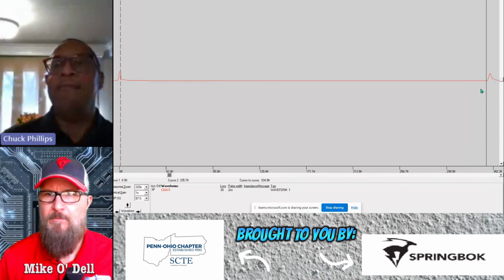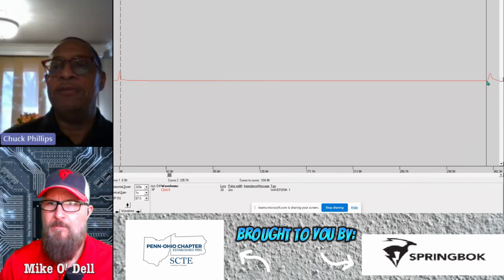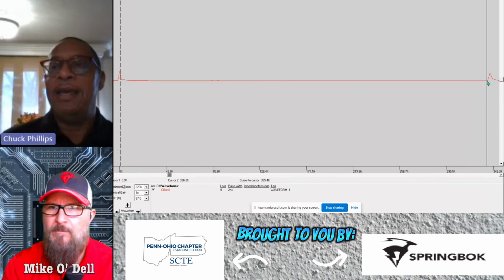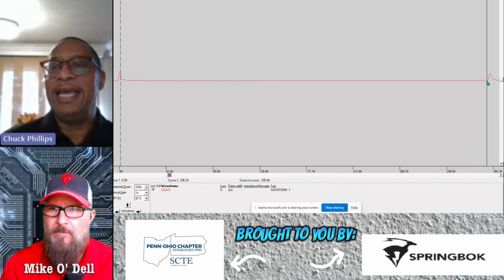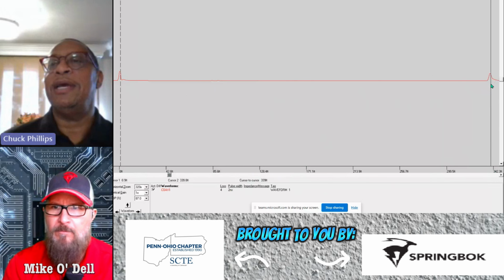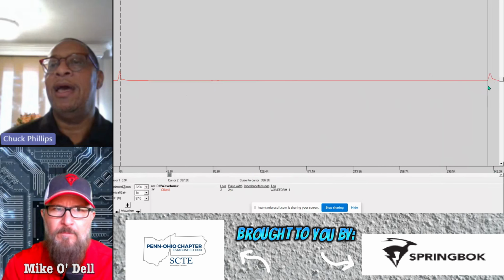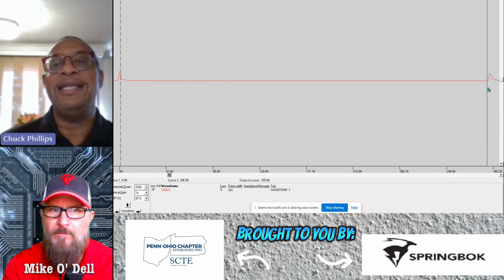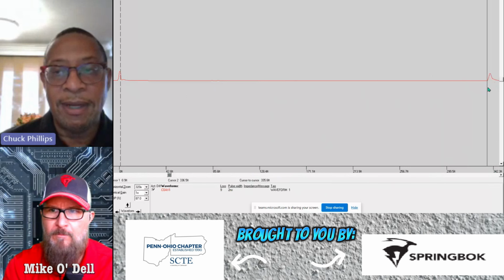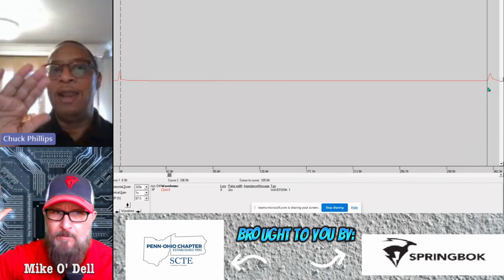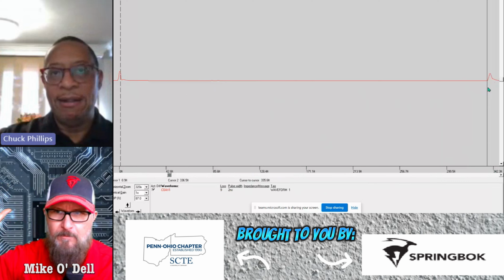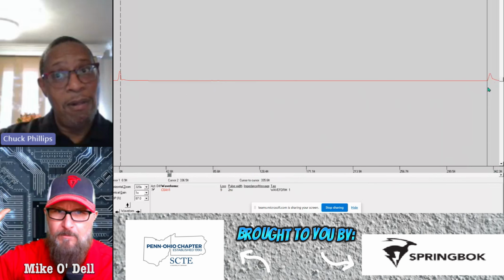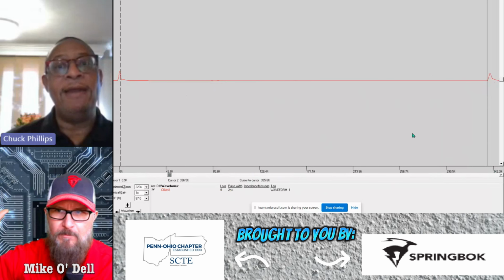334.9 feet. And by the way, perfect measurement on any waveform is going to be on the front leading edge. I don't want you to measure at the peak of the signature. I want you to measure on the front leading edge of the signature. Okay? Now, if you just want to know an about, it's not that big a deal. But if I'm the one digging the hole, right on the front leading edge, okay?